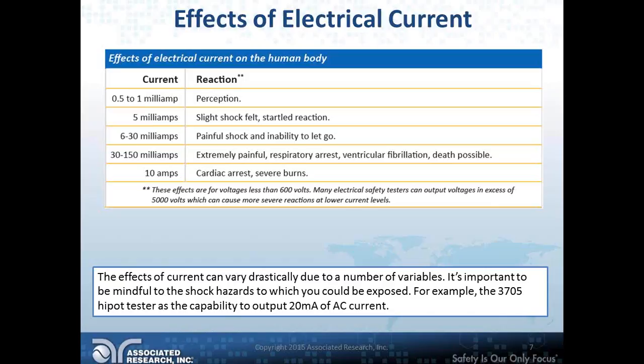Many electrical safety testers, our equipment included, can output voltages in excess of 5,000 volts. These can cause much more severe reactions at much lower current levels. To my knowledge, this hasn't really been studied in depth, but I always considered it from the standpoint of: if these reactions are documented for less than 600 volts and I'm dealing with thousands of volts, I'm going to be very careful and set up as safe a workstation as I can to make sure this never happens.